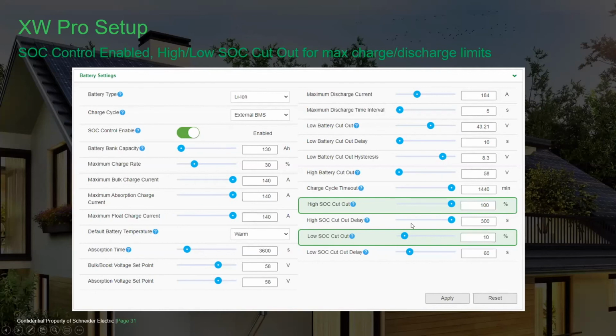So the high SOC cutout I have set up for 100%. The low SOC cutout I have set up for 10%. So it's going to load shave down to 15% and stop. If it stays that way long enough and the grid doesn't come back, it'll discharge down to 10% before it goes into a low battery condition.